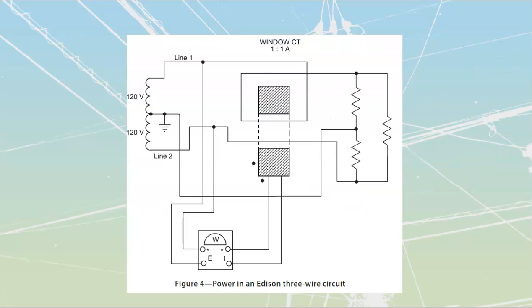Last one that we're going to talk about is power measurement, or watts reading, anytime that I have a 3-wire circuit. In other words, a 120/240 or an Edison style of circuit. Let's take a look at this one over here. What we see is we've got a single window or a single donut that has been made over here. So we'll just draw that thing out. What we need to do is make sure that our currents, if I had an Edison type of circuit and I passed both lines through in the same direction, coming from a transformer, this causes issues.